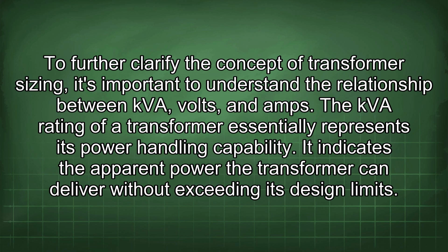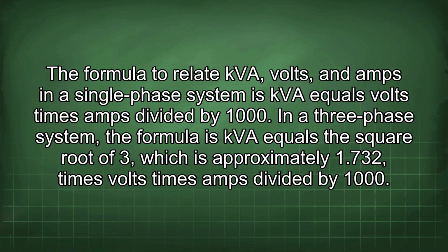To further clarify the concept of transformer sizing, it's important to understand the relationship between kVA, volts, and amps. The kVA rating of a transformer essentially represents its power handling capability. It indicates the apparent power the transformer can deliver without exceeding its design limits. A formula to relate kVA, volts, and amps in a single-phase system is kVA equals volts times amps divided by 1000. In a three-phase system, the formula is kVA equals the square root of 3, which is approximately 1.732, times volts times amps divided by 1000.